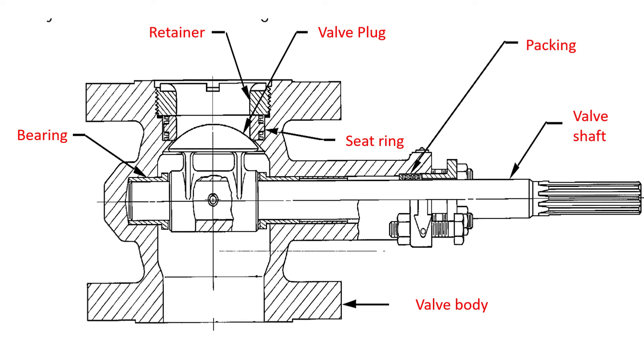The bearing — sometimes called a bushing — locates and supports the valve shaft; that is its main application. Finally, the packing is used to arrest process fluid leakage along the valve shaft to the outer area of the control valve. These are the internal components of the rotary shaft valve, similar to the sliding stem control valve, with the bearing and bushing being the distinguishing elements.